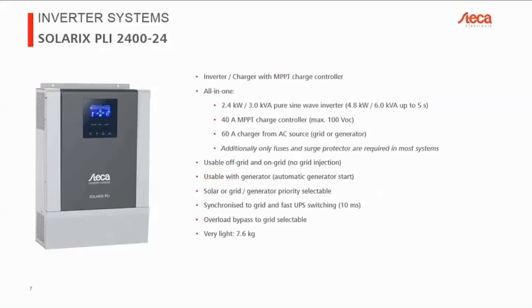So next we have the SOLARIX PLI family of inverters. Here we have 2 inverters. This is the smaller one, the 2400-24. Again, this is the power. In this case, it's the same as the nominal power, but this is always the P30, so the 30-minute power, and this 24 means that's the nominal battery voltage. So here we can have 2.4 kilowatts at a 24-volt battery system.